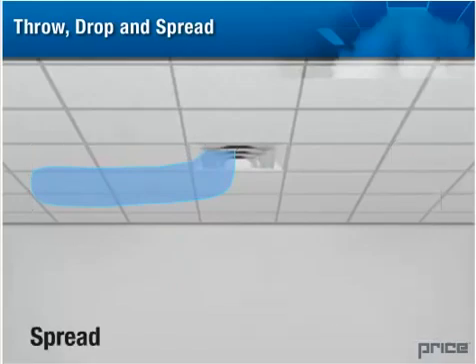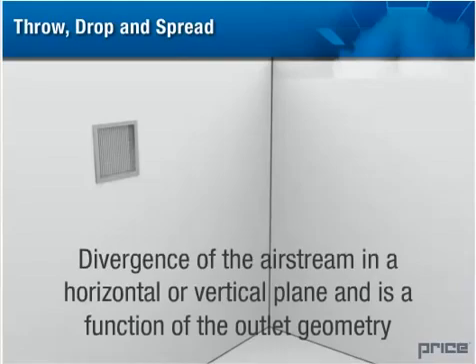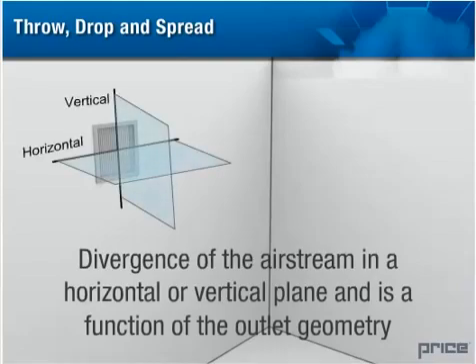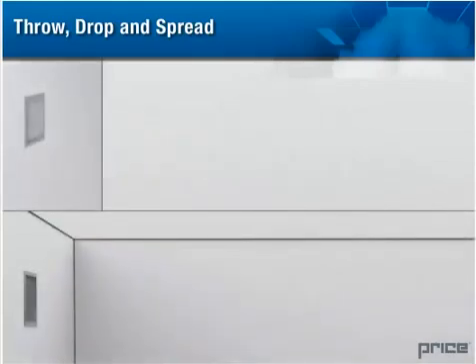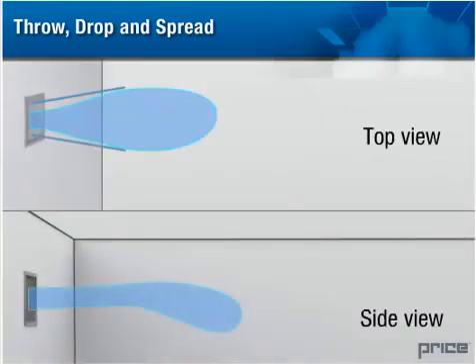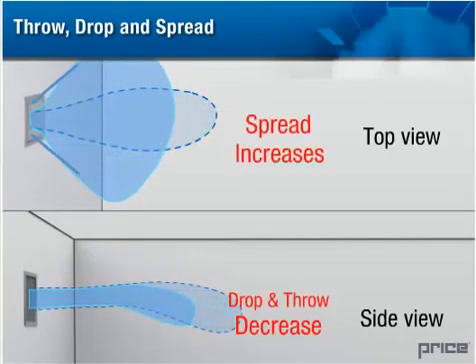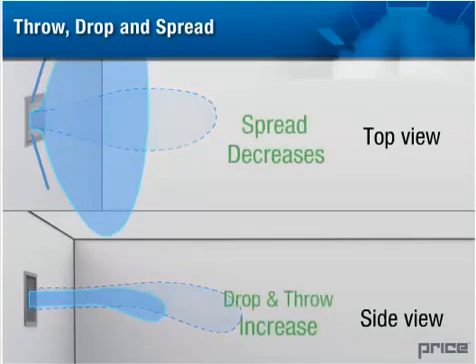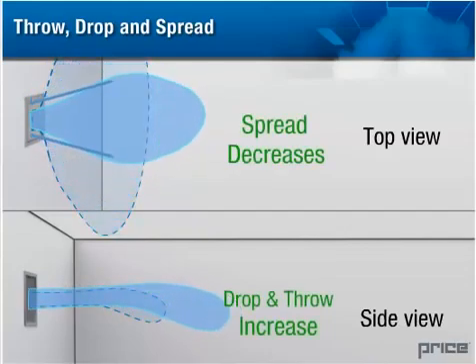Warm air is less dense and tends to rise toward the ceiling, resulting in longer throw distances and less drop. The spread of an outlet is defined as the divergence of the airstream in a horizontal or vertical plane, and is a function of the outlet geometry. As spread increases, both drop and throw decrease; conversely, as spread decreases, both drop and throw increase.